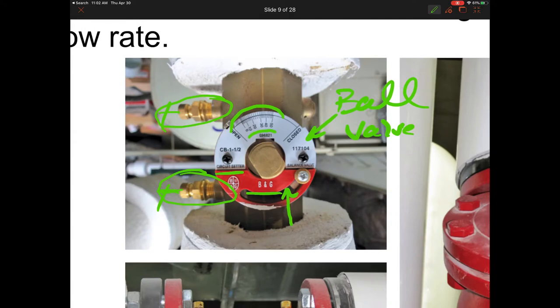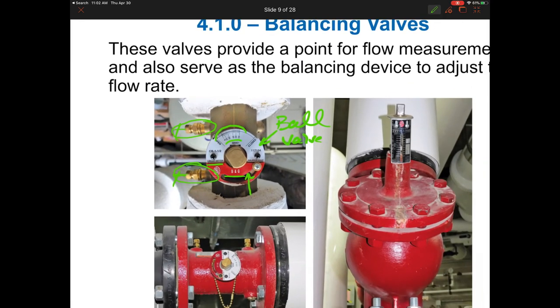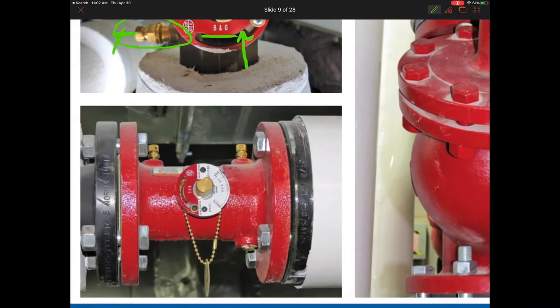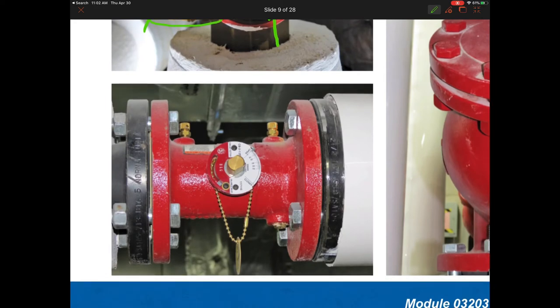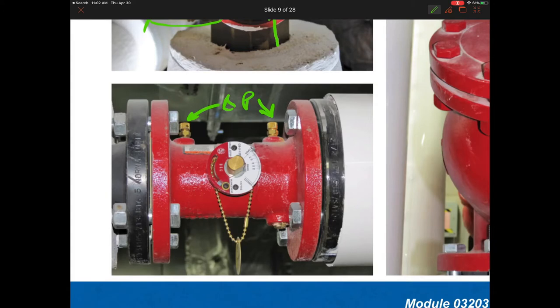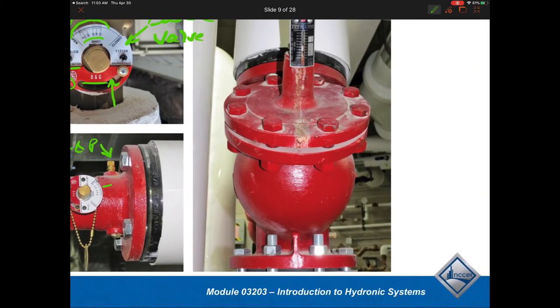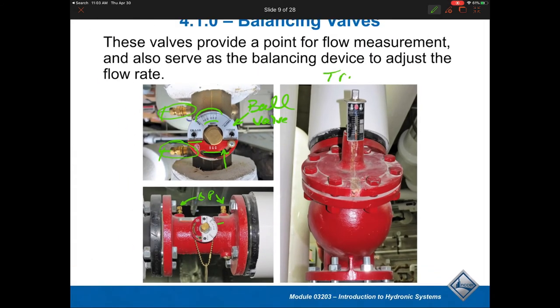This circuit setter is probably not the most accurate of valves. The biggest reason is that you have a ball valve between the two ports, which creates a fair amount of turbulence in the downstream port. So depending on the direction of water flow, one port will be very stable while the other will have a lot of turbulence, making some of the accuracy readings questionable. That said, this instrument has been around for many years and there are other types that might be more accurate, though with a cost associated with that accuracy.